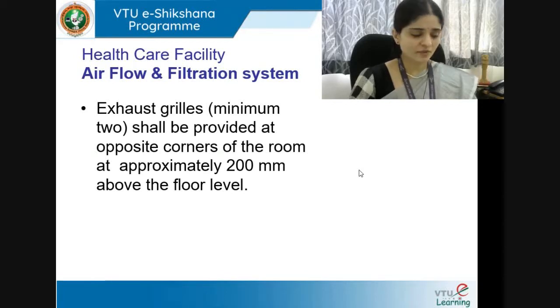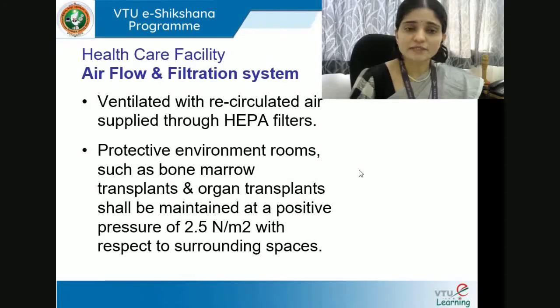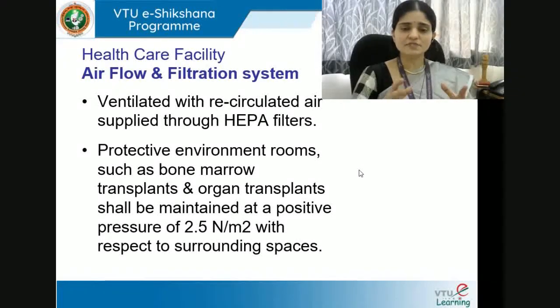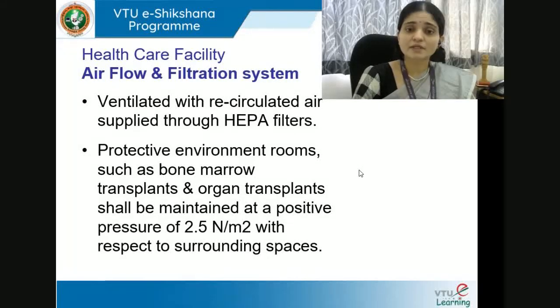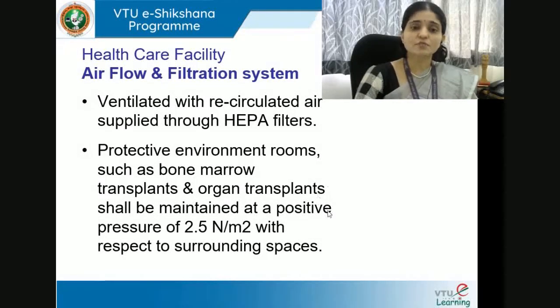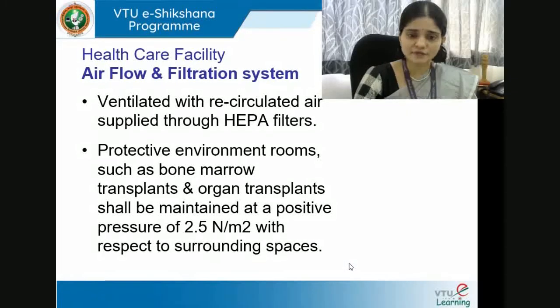For operating rooms and procedure rooms where patients are highly susceptible to infection — such as orthopedic and cardiac operating theatres — a laminar airflow system is advisable. HEPA filters on the ceiling give out cooled clean air in a downward draft, with return air grills and an influx of fresh air. Unidirectional airflow at a velocity of 0.45 ± 0.1 meters per second is advisable. The area of the laminar flow grid shall extend a minimum of 450 mm beyond the footprint of the operating table on all sides. Additional supply diffusers may be provided. Exhaust grills — minimum two — shall be provided at opposite corners of the room at approximately 200 mm above the floor level.